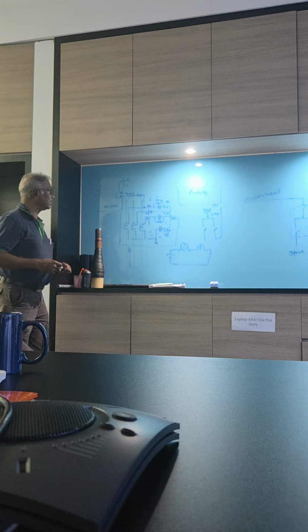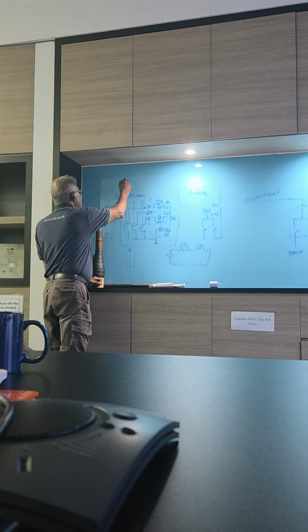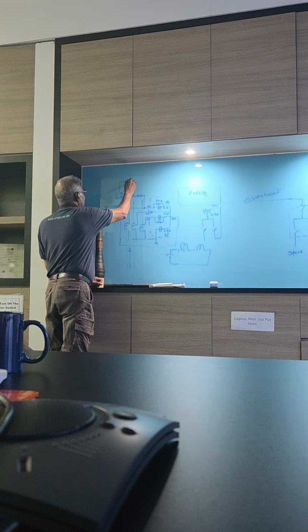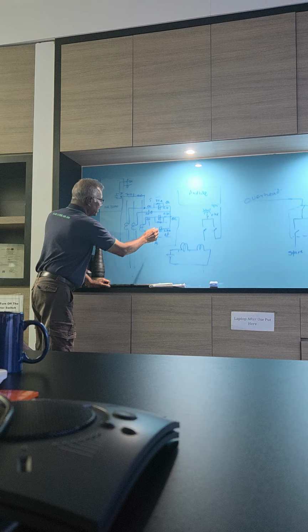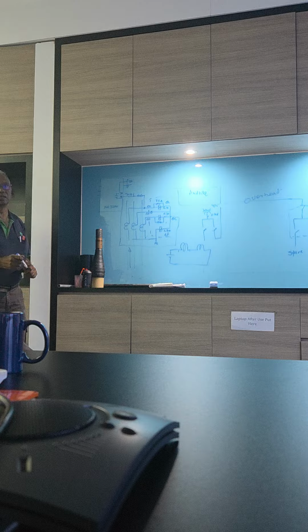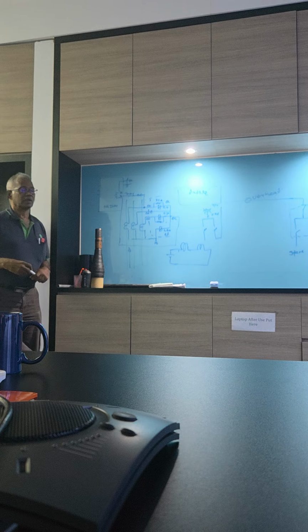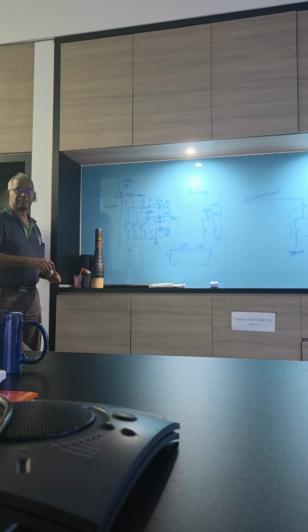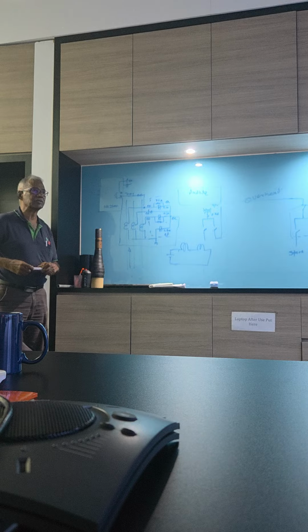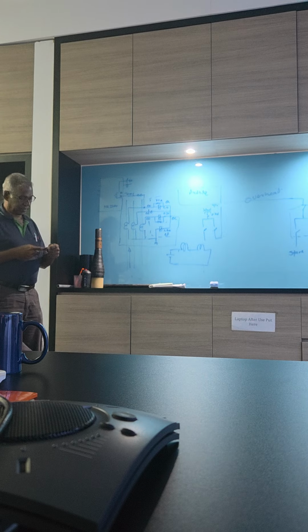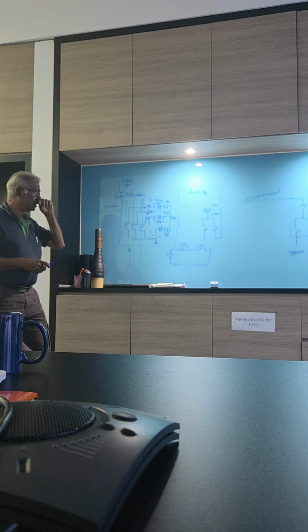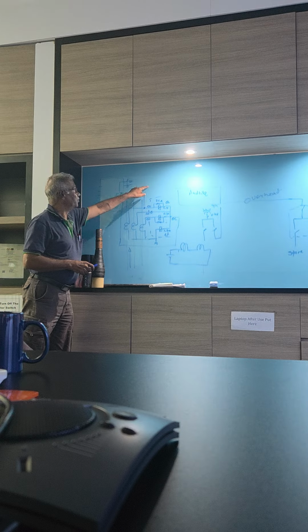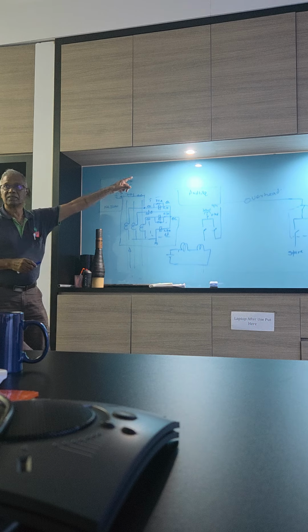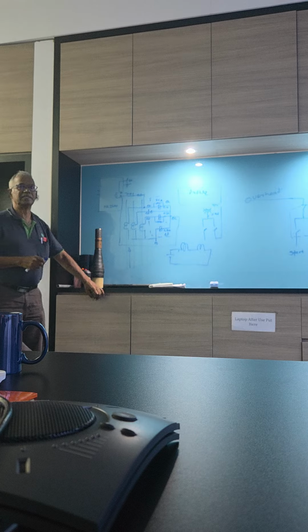So when they were tracing, they said, why can I get 30 volt here, and here when they measured it, it was only 16 volt. There was one time I experienced this. If you have that, you must go straight to the battery bank, the battery charger, the DC battery charger. They have a few lights, see if any are blinking. So I went, and there is a DC fault.